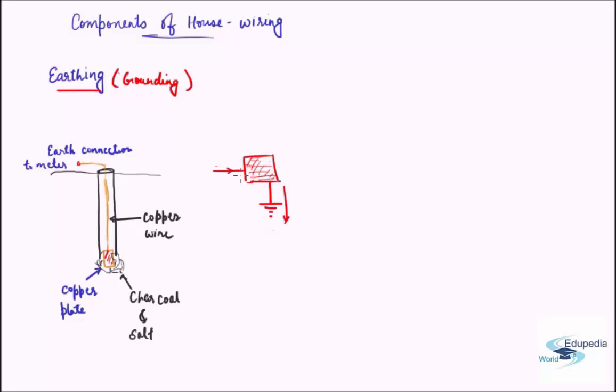If a person accidentally touches this, they might get electrocuted. But in such a scenario, since the current has immediately gone to a very high value, the high flow of current will lead to the breaking of the fuse and the system will secure itself. You will come to know there is some problem in the system, and while inspecting you will be able to find out where exactly the problem occurred, avoiding any unforeseen circumstance. So this is the basic concept of earthing or grounding.